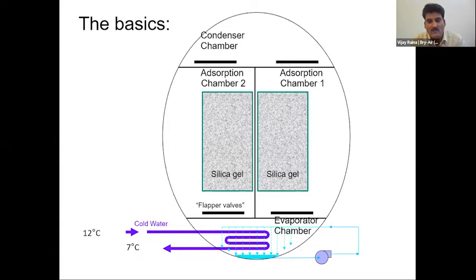Because this is a vacuum based chiller, we create a vacuum for water to evaporate at a very low boiling point. So when we maintain a vacuum in a closed vessel, it's simple chemistry that water boils at a low boiling point. The boiling point of water is only 6 degrees at 10 to 15 mm of mercury pressure. At atmospheric pressure, it boils at 100 degrees centigrade, and under vacuum, it boils at 6 degrees centigrade. So in the evaporation chamber, we have refrigerant water filled initially in the chiller, and then we take a load from the AHU at 12 degrees. The refrigerant water at 6 degrees boiling point gets evaporated.